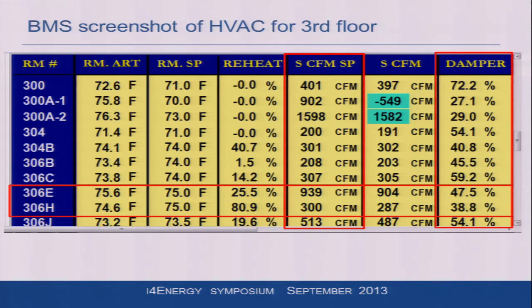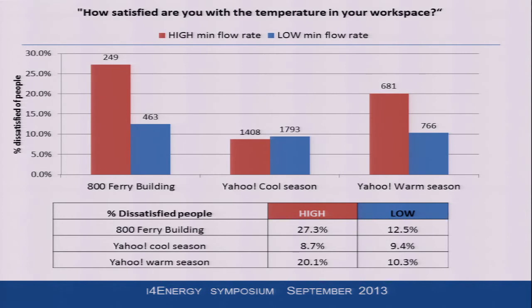but you can see here that in these zones, which got two people and one person in them, you've got on the order of 900 and 300 CFM going to the room. Now, for one person, you need 15 CFM. So we're running 20 times the air that we need. And it's cold air because the building is essentially an internal-dominated building. So this building has got its dampers closed. It's straining to provide this huge amount of pre-cooled air to just a few poor people who are sitting there being frozen. And there's a lot of complaints about it.